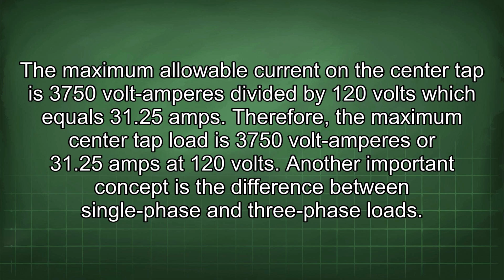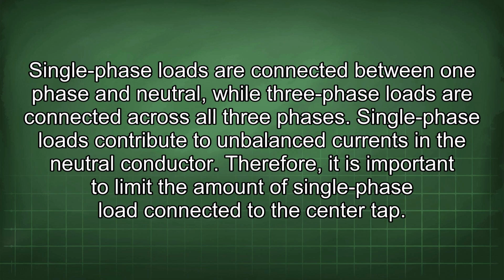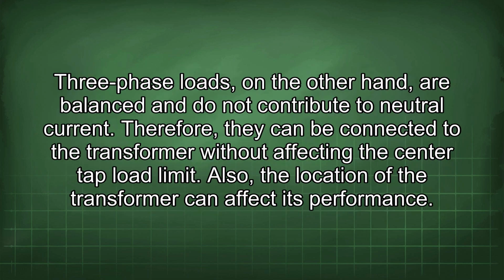Another important concept is the difference between single-phase and three-phase loads. Single-phase loads are connected between one phase and neutral, while three-phase loads are connected across all three phases. Single-phase loads contribute to unbalanced currents in the neutral conductor. Therefore, it is important to limit the amount of single-phase load connected to the center tap. Three-phase loads, on the other hand, are balanced and do not contribute to neutral current. Therefore, they can be connected to the transformer without affecting the center tap load limit.